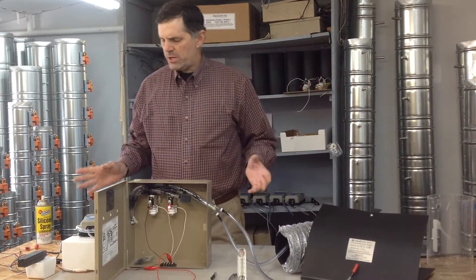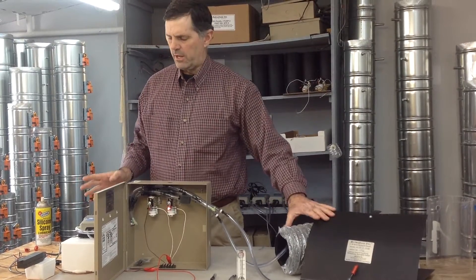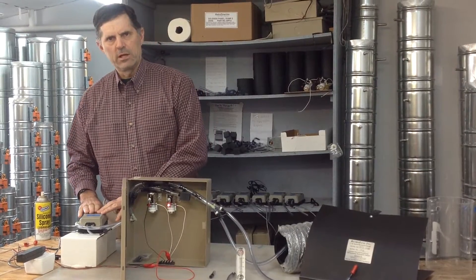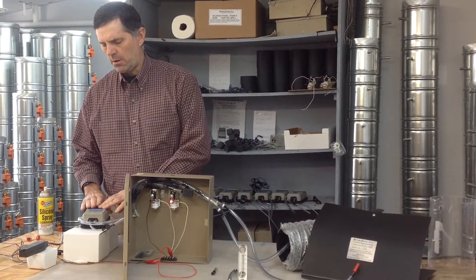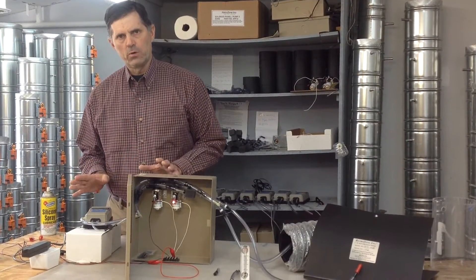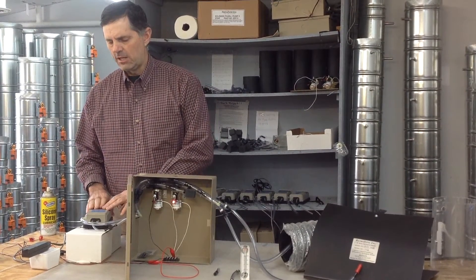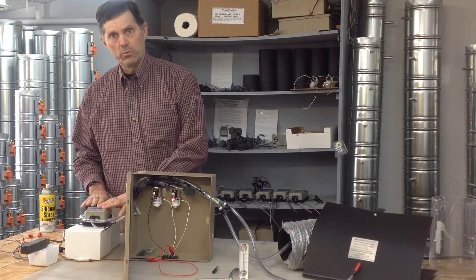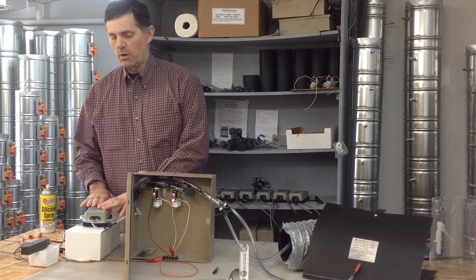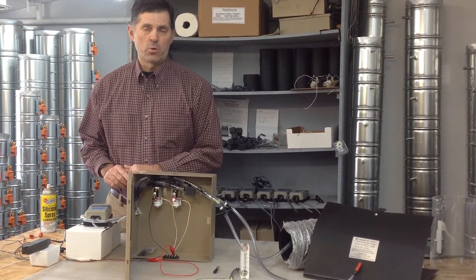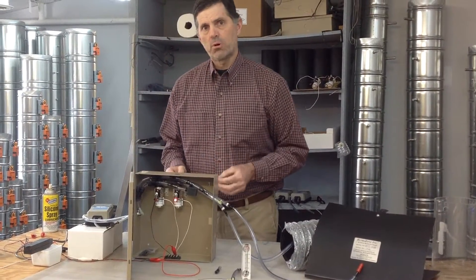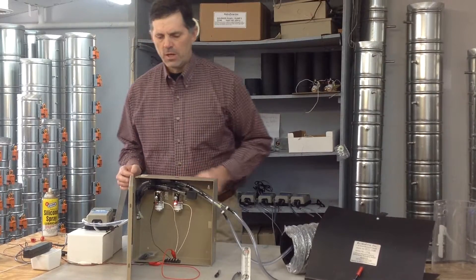Now, the major components of the system are simply the dampers, the pump that I briefly talked about. That pump has got a couple of relays in it that are tied into the equipment side of your heating and air conditioning unit. It's all low voltage, but it does tie into the fan and to the furnace circuit, so the pump only runs when the heating and air conditioning equipment is running. The pump is running right now. I don't know if you can hear it or not, but it is very quiet. It's a vibration style pump that provides both pressure and vacuum.